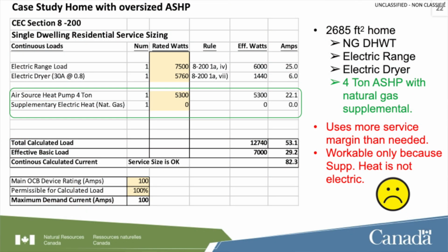We're going to oversize the air source heat pump just for giggles. So again, we've got our effective base load at 29.2, and we've added the air source heat pump with a 4-ton unit, which uses 22.1 amps. So we're still within range, but it's not going to give us a whole lot of room for anything further.